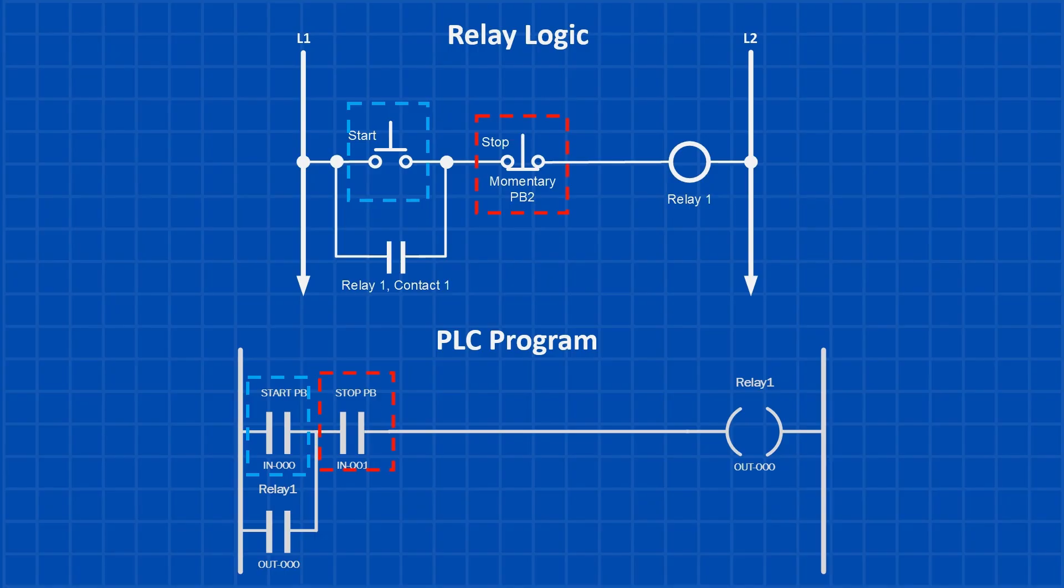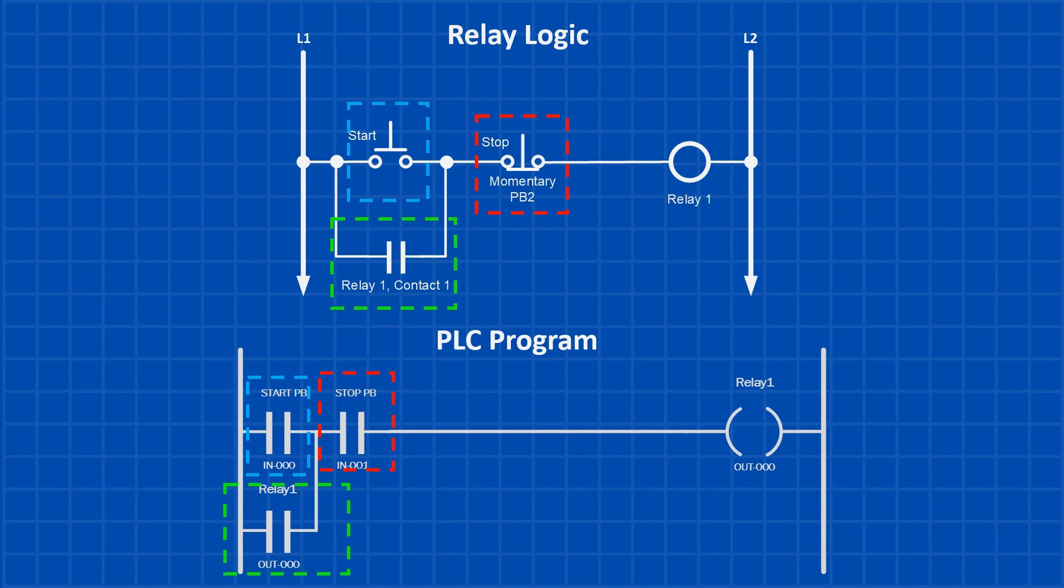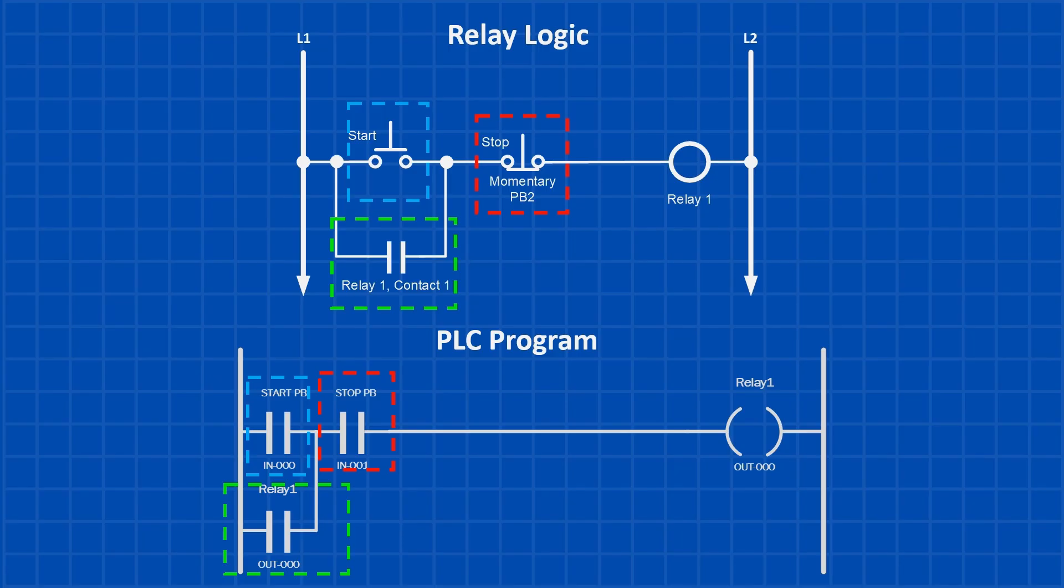To create the latch, we use Out-0-0-0 as a contact in parallel with the start push button, just like we did with the relay's contact in the previous example. Now here's something important. Even though the stop button is a normally closed contact in the real world, we represent it as a normally open instruction in the PLC program, because the PLC logic sees it as closed when it's not being pressed.